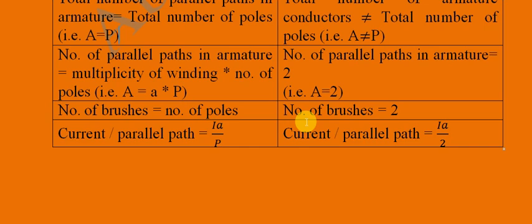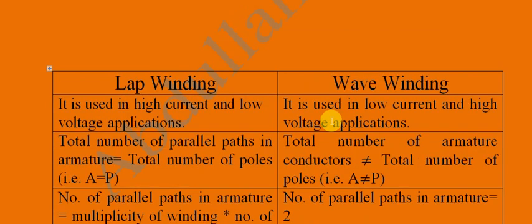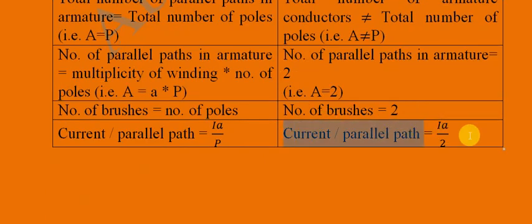In wave winding, the number of brushes is always 2, and the number of parallel paths in the armature is also 2. For current per parallel path: in lap winding it is Ia divided by P (armature current divided by number of poles), and in wave winding it is Ia divided by 2.